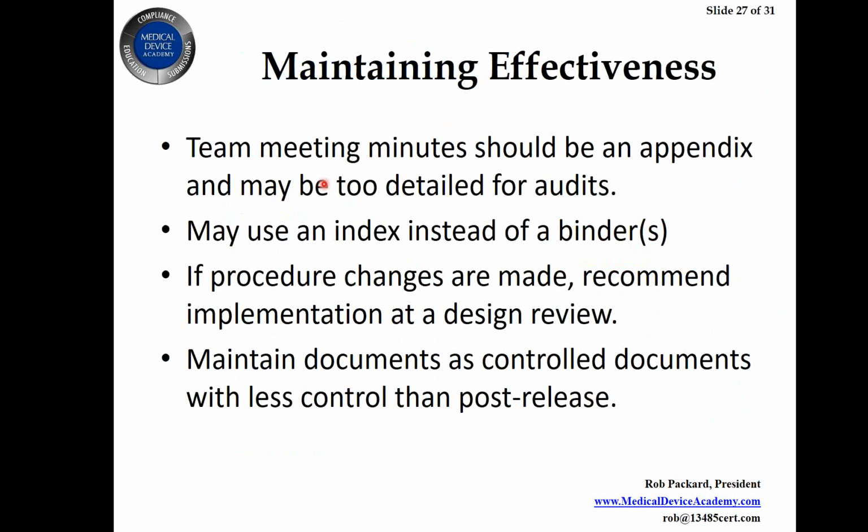You might use an index if you want to instead of binders, but I tend to use indexes only for the device master record and the technical file, not for the design history file, because you really want it to follow your design plan. And if procedure changes are made, I said implement those at the design review, and maintain all the documents as controlled documents.